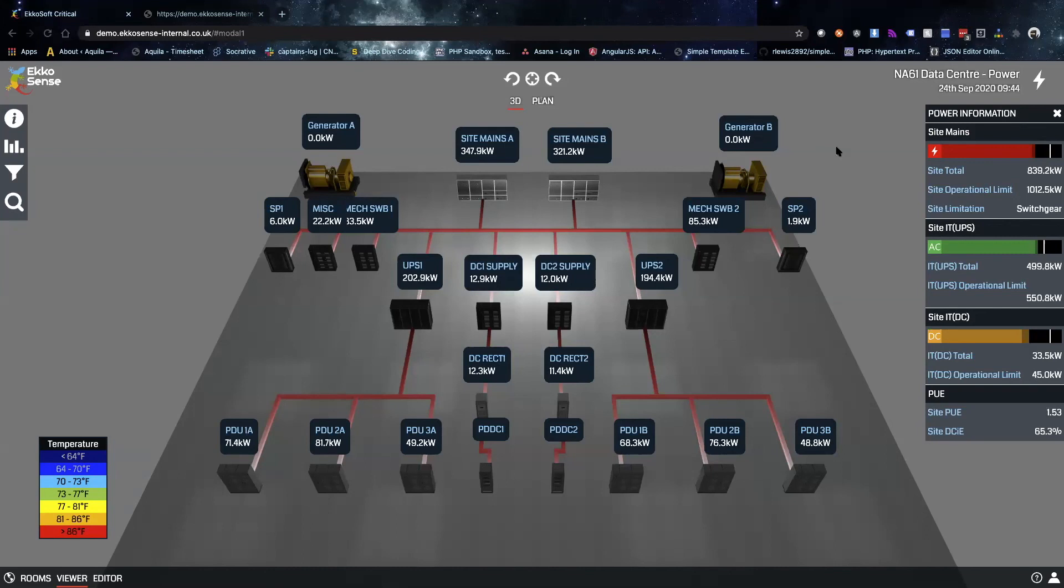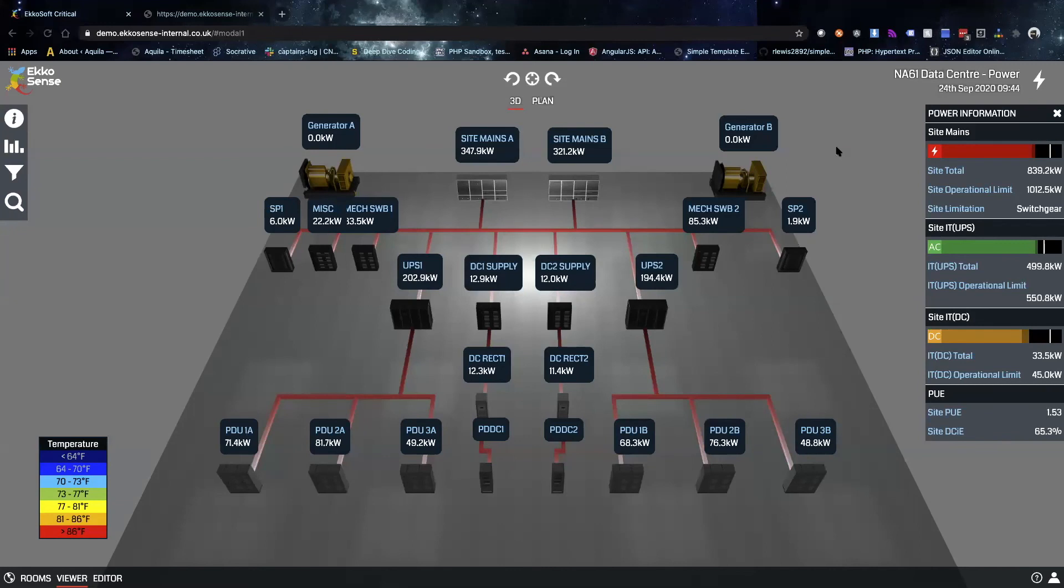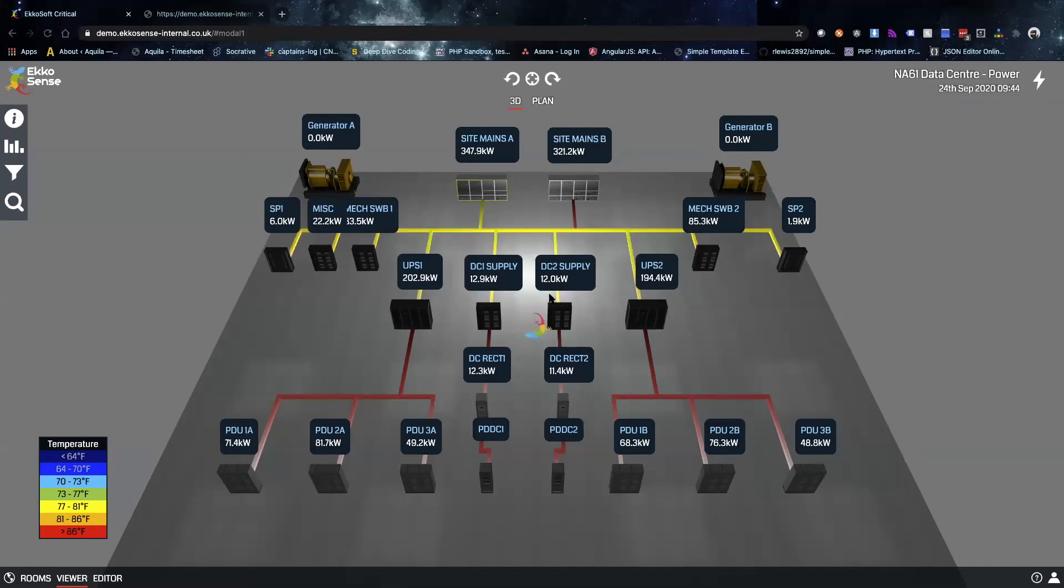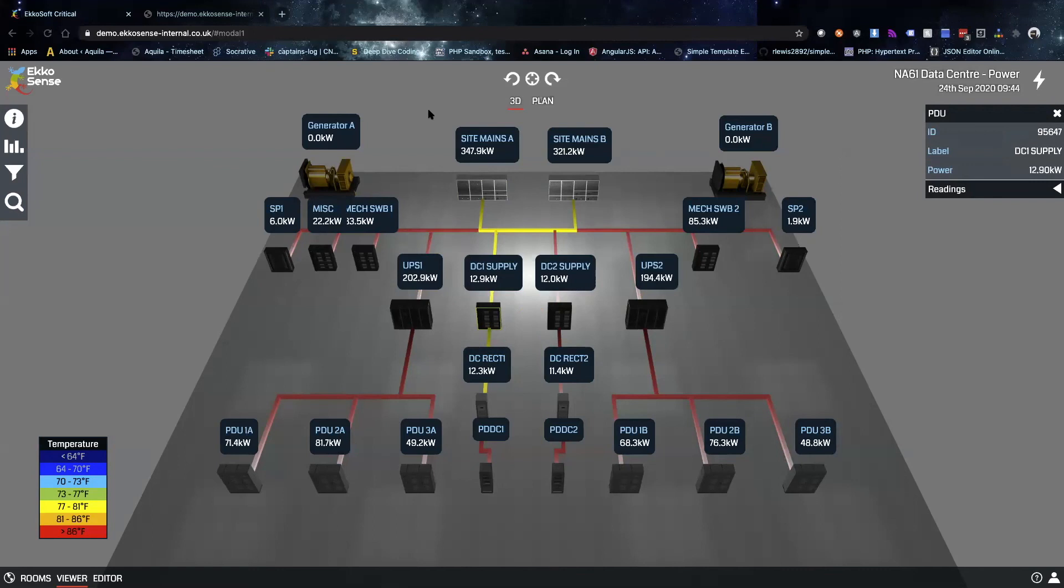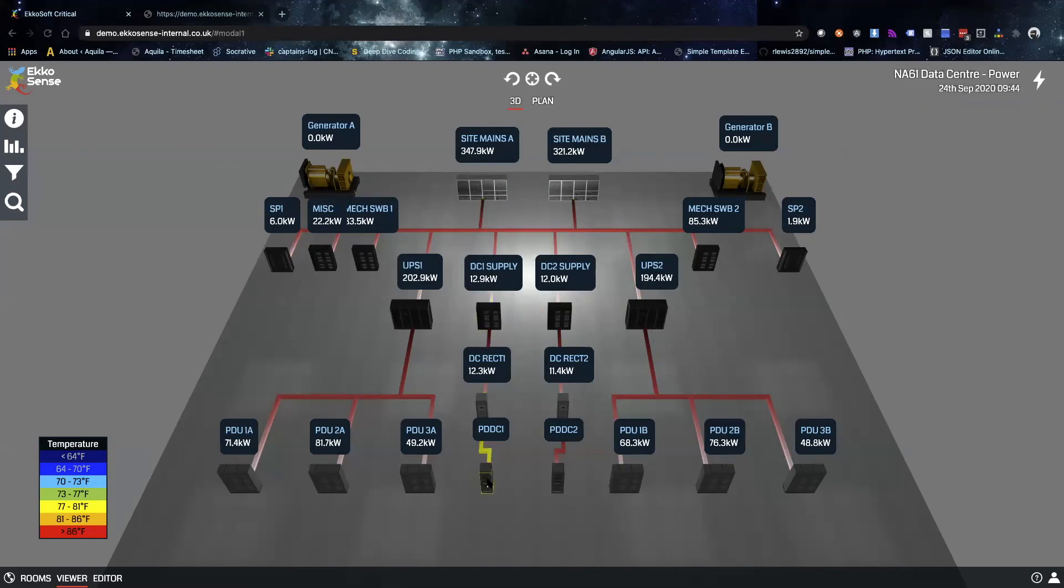Distribution boards, main income, PDUs is usually Modbus and we'll just pull the registers and then give you the real-time power views in a nice immersive way. You can click on any of those components and get the data, you can graph it or whatever data you want. Bring it to the capacity module, look at site metrics in terms of CPU, in terms of PUE, DCiE, etc. All feed into the estate view to look at overall power capacity, AC or DC, and you go all the way from mains incomer down to rack level if you should wish.